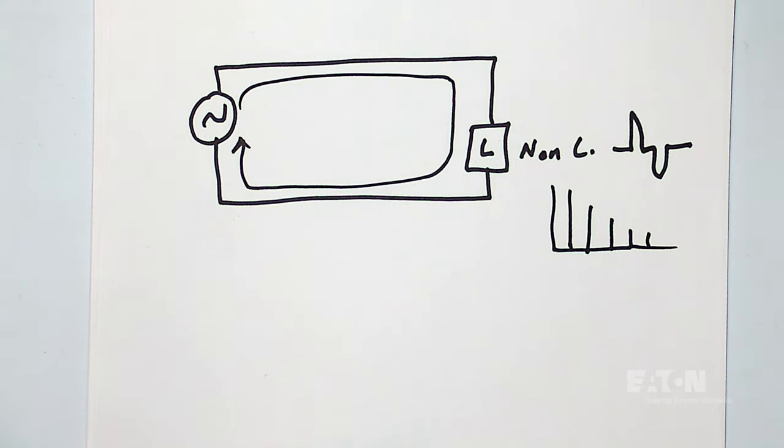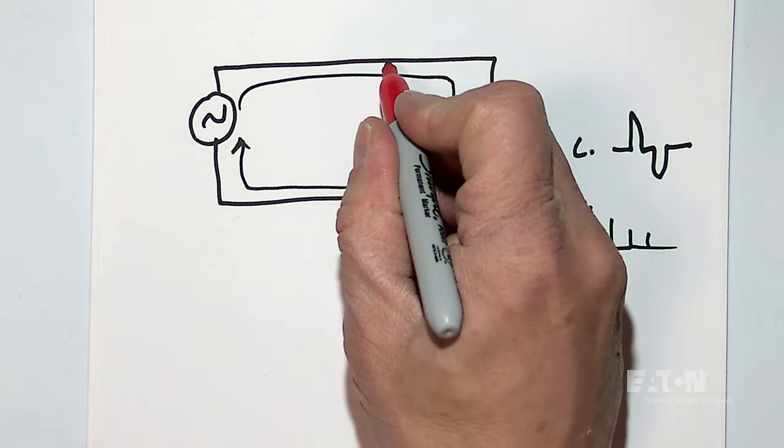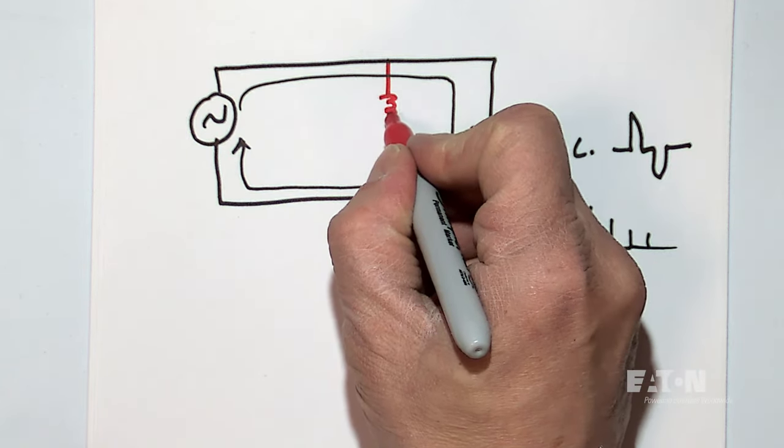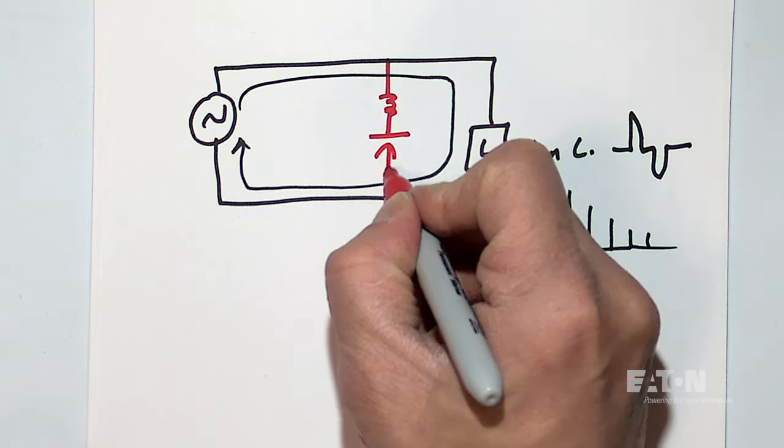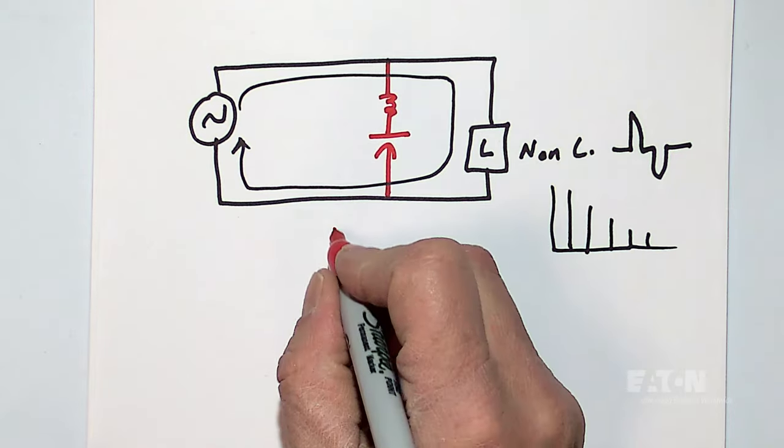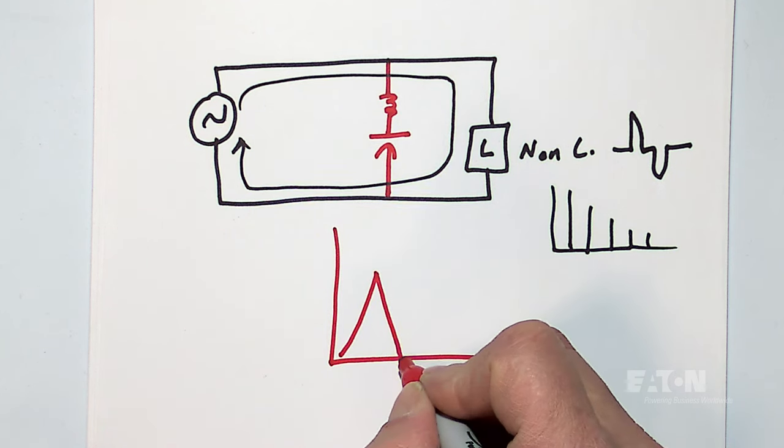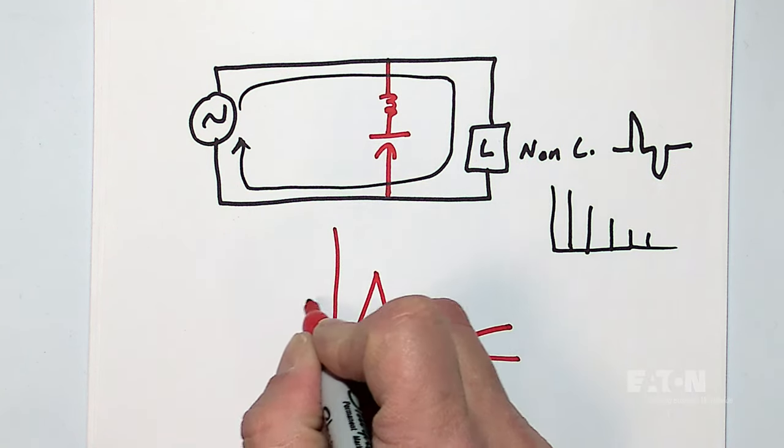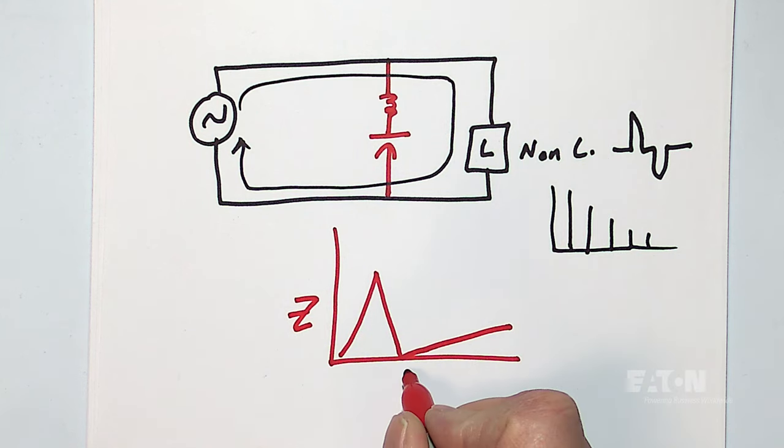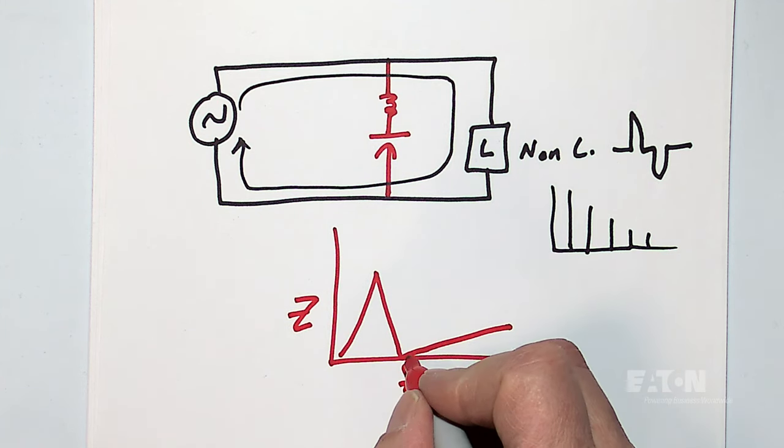So if I put a harmonic filter in the path before the load but after the source, what's a harmonic filter? Basically an inductor tuned with a capacitor and I tune it so that my frequency of tuning is very low impedance at whatever frequency. So let's say I tune it to just below the third harmonic.